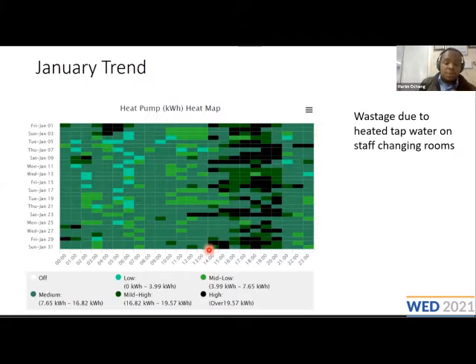And as you can see, from around 2 p.m. to around 9 p.m. daily, there was a significant increase in energy consumption on the heat pump section. And through the energy committee meeting, we were able to identify that this consumption, might have been coincidental, appeared mostly during staff changeover, scenarios where staff were changing shifts. Drilling down a little bit further, we identified that in the staff changing rooms, the taps themselves, basically taps for washing the hands and a couple of other things, were mostly heated, drawing power from the heat pump.